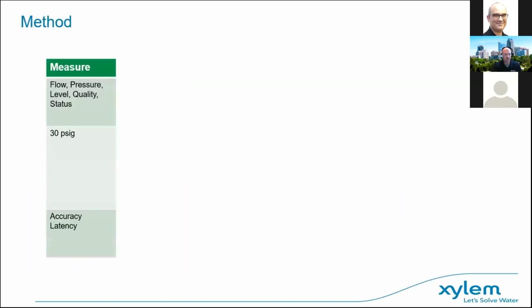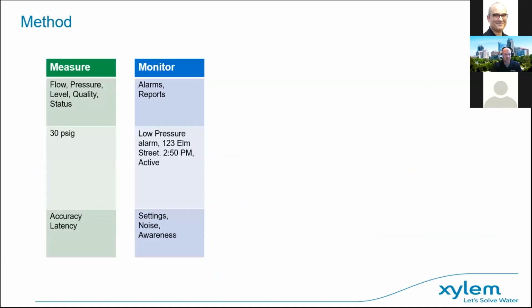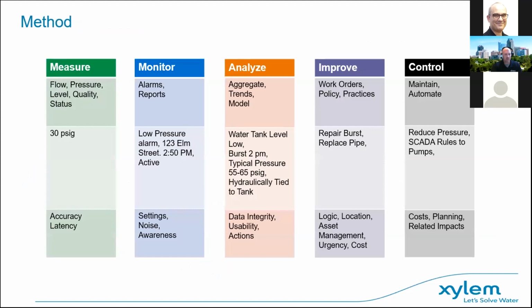That methodology looks like simple engineering classic activities: measure, monitor, analyze, improve, and control. I listed one simple example here. We might measure things like flow, pressure, level, quality, status — you see an example of 30 PSI. But there are some gotchas: what's the accuracy of that measurement? How latent is it? You might only begin to monitor for when it has gone awry from that baseline.